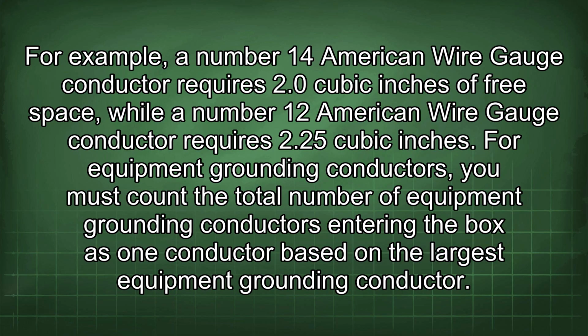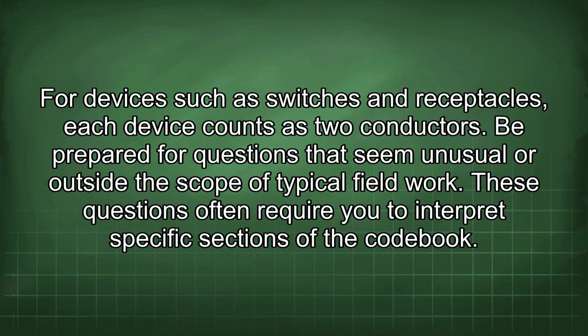For equipment grounding conductors, you must count the total number of equipment grounding conductors entering the box as one conductor based on the largest equipment grounding conductor. For devices such as switches and receptacles, each device counts as 2 conductors.